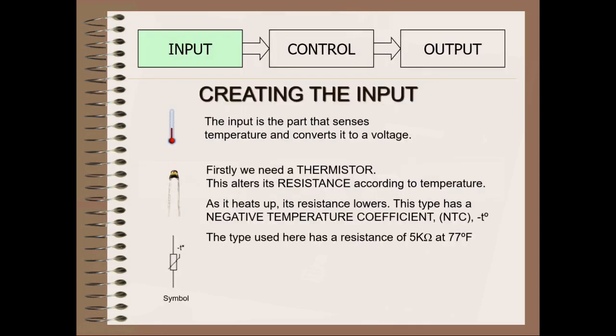So in creating the input, this input is the part that senses temperature, converts it to a voltage. Firstly, we need a thermistor. This alters its resistance according to temperature. As it heats up, resistance lowers. This type has a negative temperature coefficient. This particular type used here has a resistance of 5 kilo ohms at 77 degrees Fahrenheit.